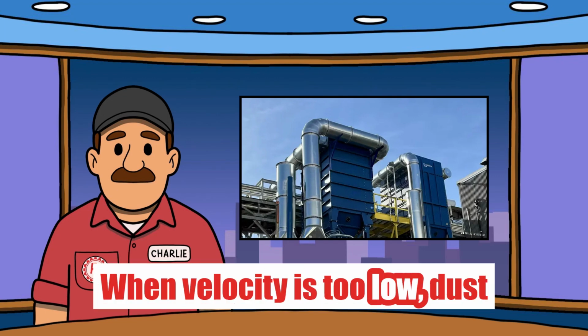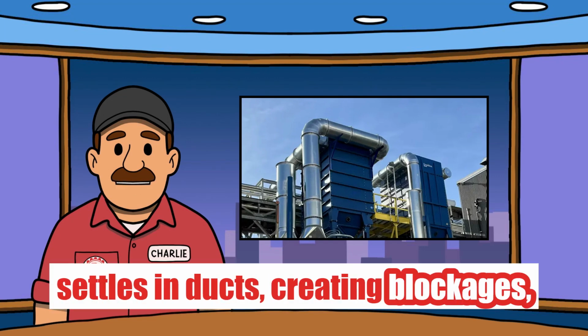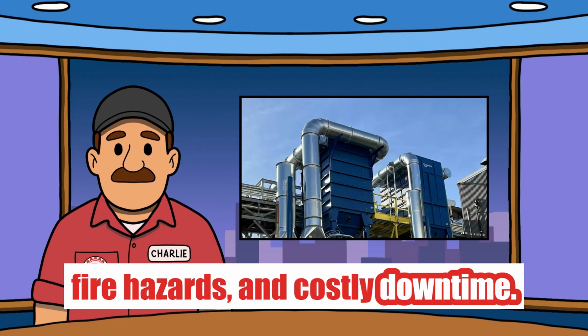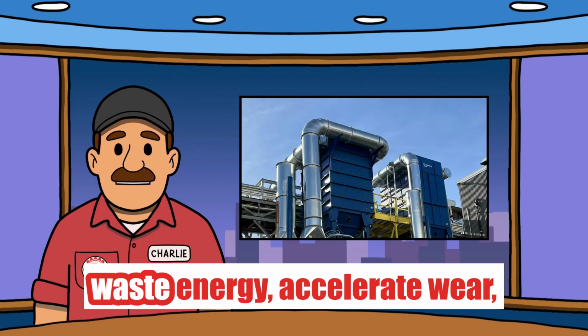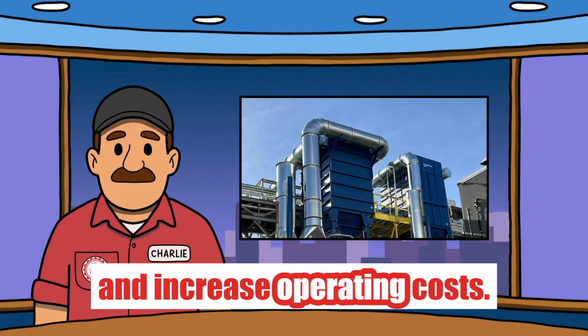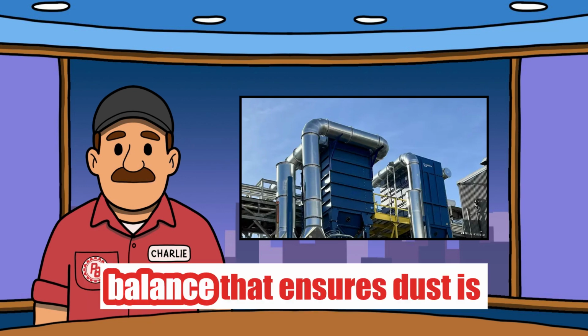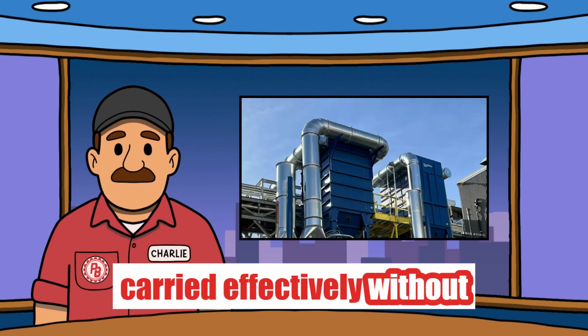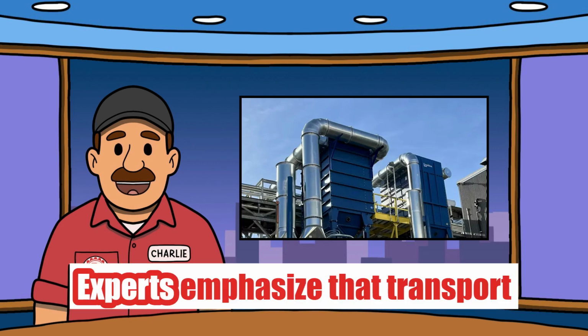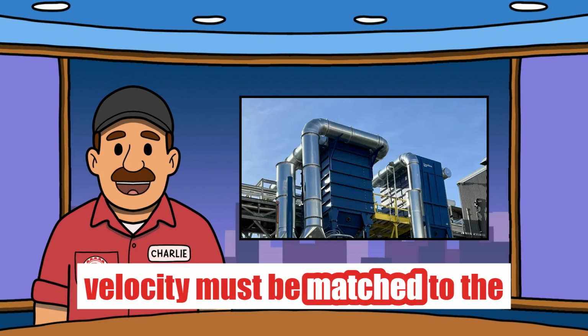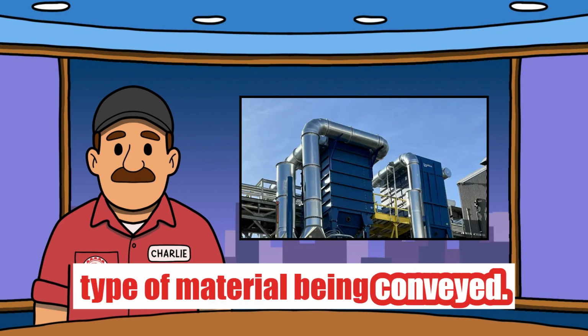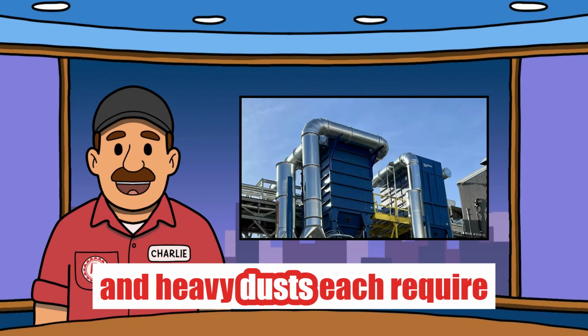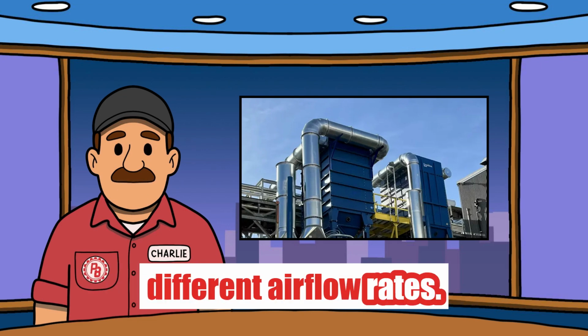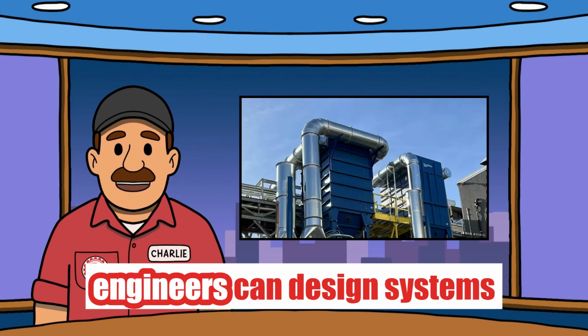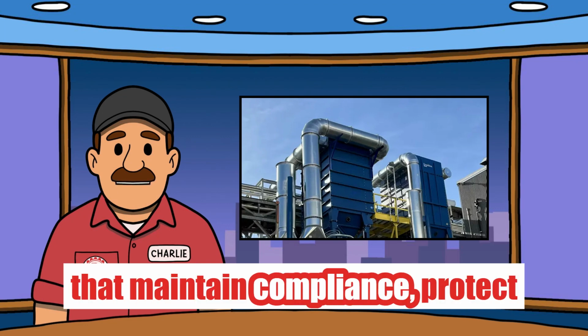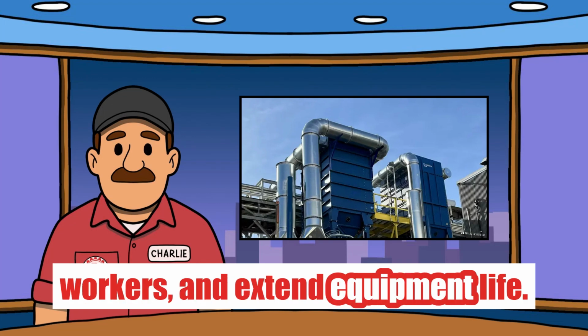When velocity is too low, dust settles in ducts, creating blockages, fire hazards, and costly downtime. When velocity is too high, systems waste energy, accelerate wear, and increase operating costs. The challenge is finding the balance that ensures dust is carried effectively without overloading the system. Experts emphasize that transport velocity must be matched to the type of material being conveyed. Fine powders, fibrous particles, and heavy dusts each require different airflow rates. By carefully calculating velocity, engineers can design systems that maintain compliance, protect workers, and extend equipment life.